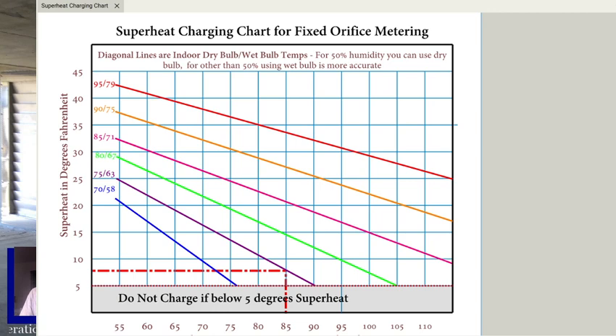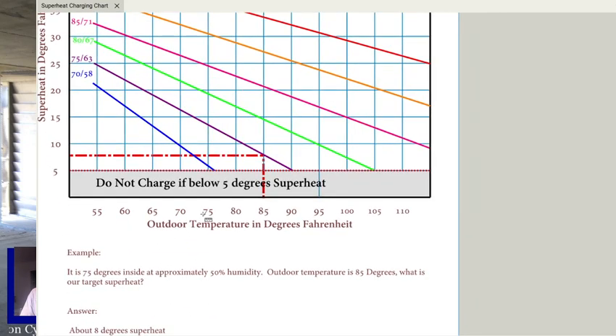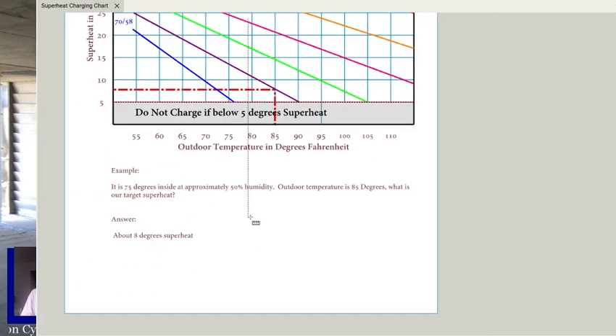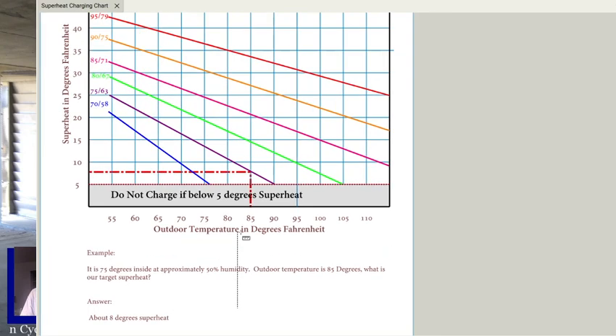All right. So anyway, if it's 75 degrees inside and 85 degrees outside, you just take your outdoor line, go up until you meet your indoor line that you're working with, and then follow that over so you can get your superheat number. So right here, we're talking about an 8-degree superheat. About 8 degrees of superheat is what you'd be looking for in that situation.